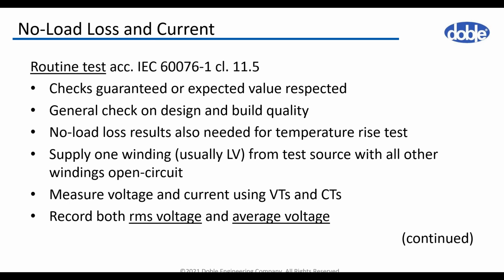No load loss and current is another performance test. Details for no load loss measurement are listed in IEC 76 part 1 item 11.5. The purpose of the test is to verify that the no load loss agrees with the limit guaranteed and with the design values. Also, results give an indication of the design and build quality of the unit. The test is important as no load losses are present once the unit is energized, and the result is used for the temperature rise test.